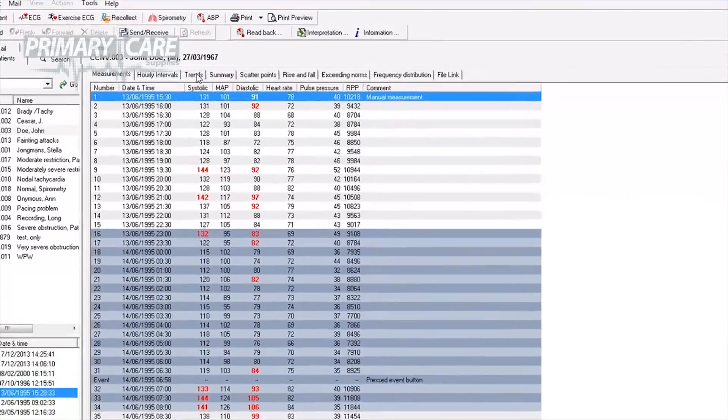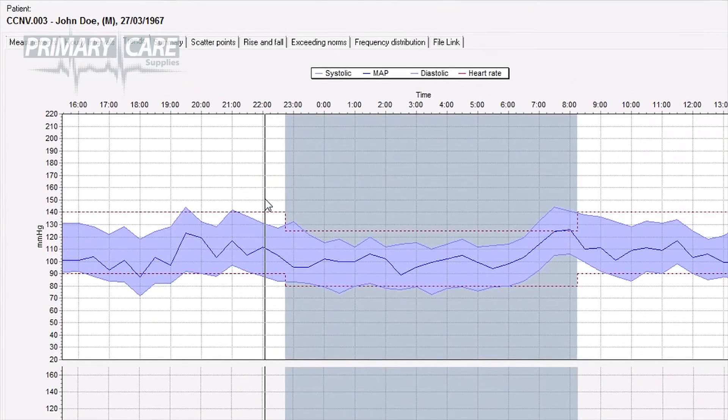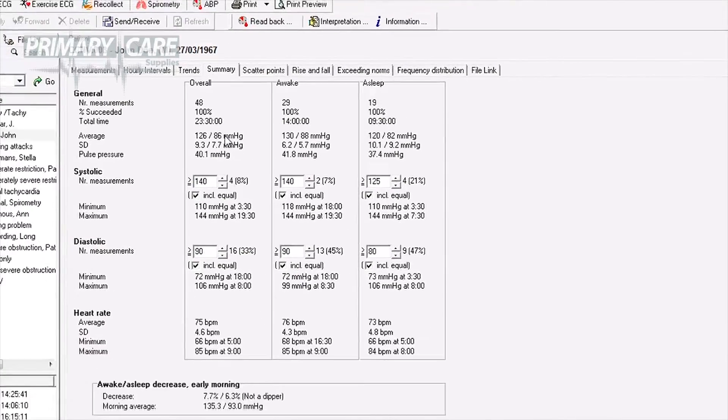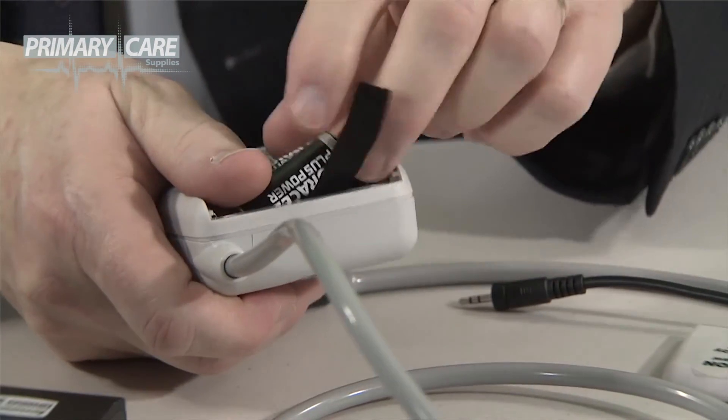You can view the results in many different formats by going into the software and selecting the tabs at the top of the screen. For example, the Trends tab will show you a graph of the entire 24 hours, and the Summary tab will give you the whole test average for systolic and diastolic readings. Any of these reports can be saved as a PDF file for attaching to your patient record system. Finally, don't forget to take the batteries out of the unit once you've downloaded the results. That's the end of this Welch Allyn ABPM training session. Thank you for watching.